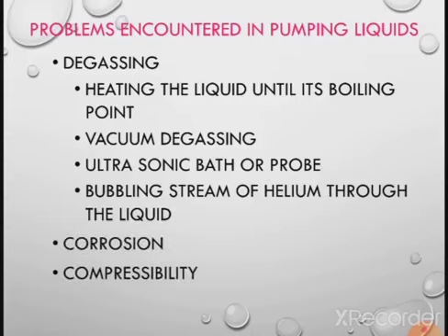The next problem is corrosion. When the mobile phase comes into direct contact with the pump, it may cause corrosion, and due to this corrosion, it may cause contamination. Another thing is compressibility. Some liquids are compressible in nature, and due to this they provide a different flow rate.